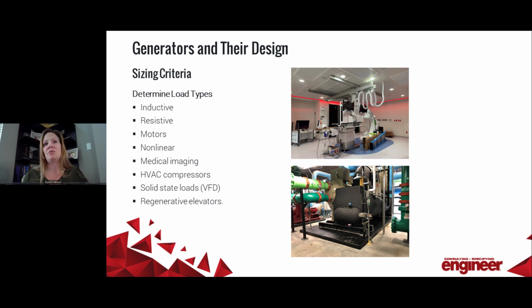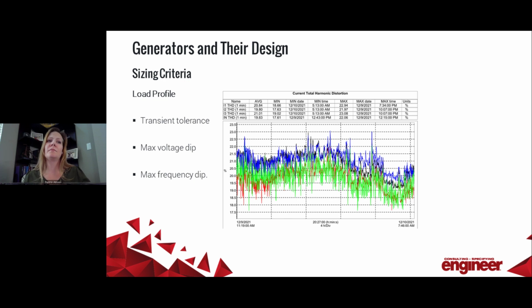So you need to ensure that your generator is large enough to handle those types of loads, or you have to guarantee that there are going to be enough loads connected to the system to use the power so that it doesn't negatively impact your generator. Through a thorough review of all of your anticipated loads, the load profile will really impact the size of the generator system. The transients or voltage dips caused by inductive loads could negatively impact any other loads already connected to the system when they're started. And the larger the motors are, the more impact they will have.